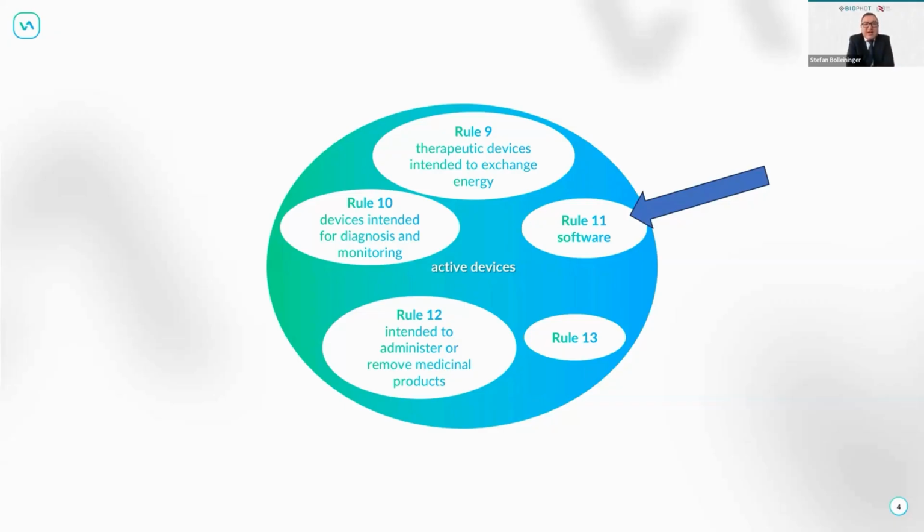works straightforward. And once your product has created sufficient revenue for making it to a medical device, then you can recreate the same product for humans, then as a medical device, and in that case this will lead to a medical device according to Rule 11, 10, 9, whatever, based on your specific product type. So yes, it is a possible pathway to go to animal usage first, and then go to humans once the data is fully available.